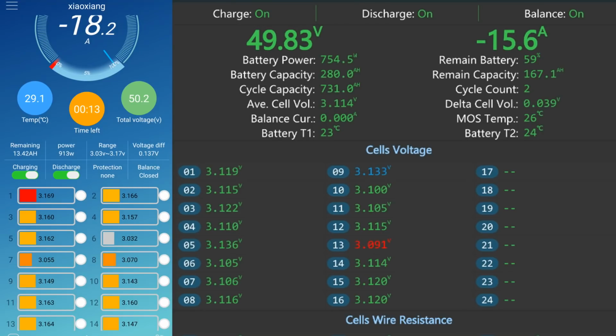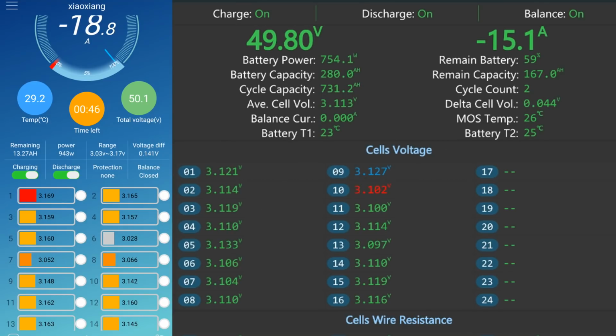And he also explained the current the inverters are pulling from a battery is not constant, because they have to invert the power from DC to AC inside and basically turn the power off and on very quickly to achieve a higher voltage inside the inverter. And this causes a certain ripple on the DC voltage, which the QUCC BMS picks up. And depending on when it measures the voltages of the cells, you could have a higher voltage or a lower voltage at this point of time of measurement.